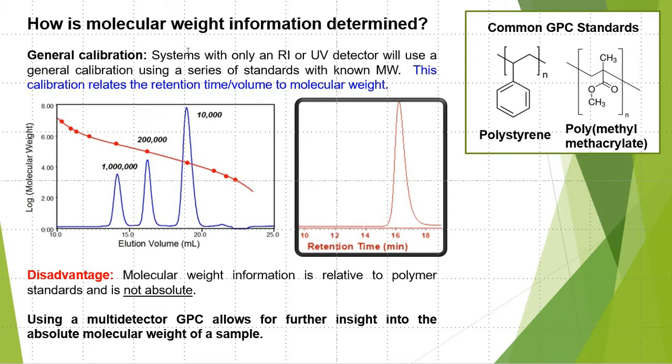A series of polymer standards, often polystyrene or polymethylmethacrylate, will be run through the instrument first. As shown here on the left, using the instrument software, it will create a calibration curve which relates the molecular weight of the standard to its retention time or elution volume.